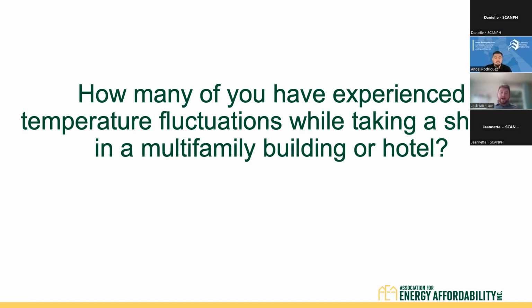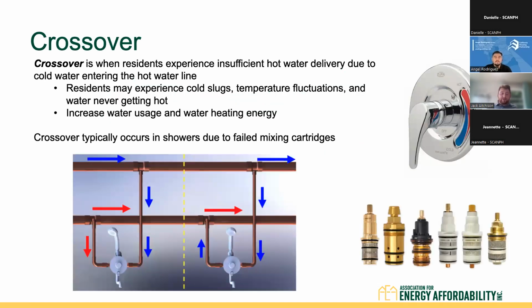The reason why we have issues with fluctuations of hot water temperatures specific to multifamily and hotels is because of the issue of crossover. Crossover is effectively when residents experience insufficient hot water delivery due to cold water entering the hot water line. So residents may experience cold slugs, temperature fluctuations, and water never getting hot. Increased water usage and water heating energy is going to be a direct result of having crossover. Crossover typically occurs in showers due to failed mixing cartridges.